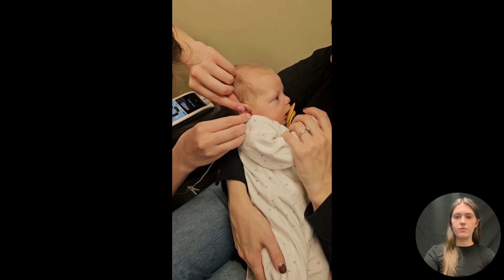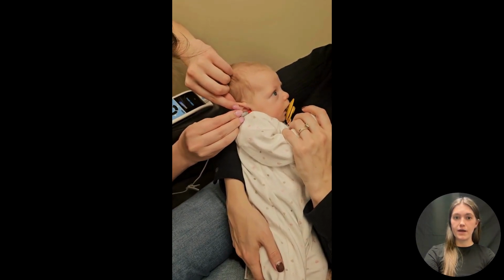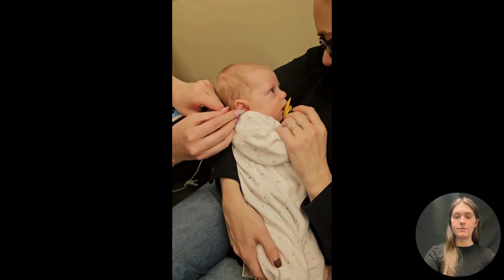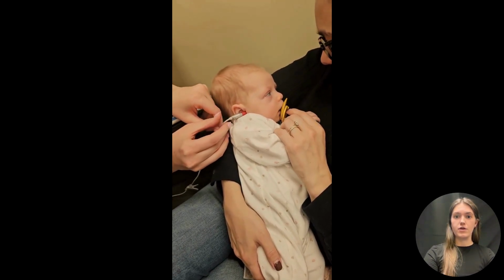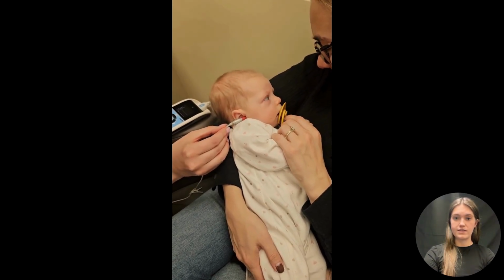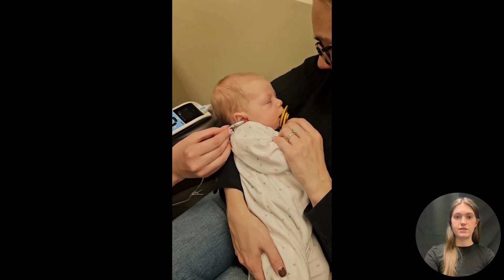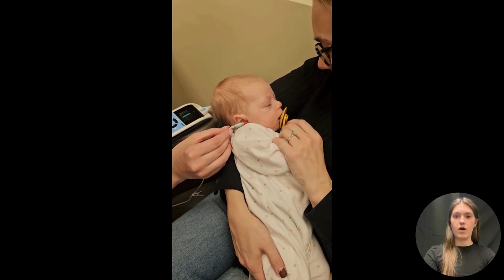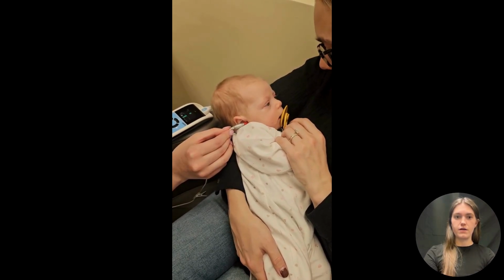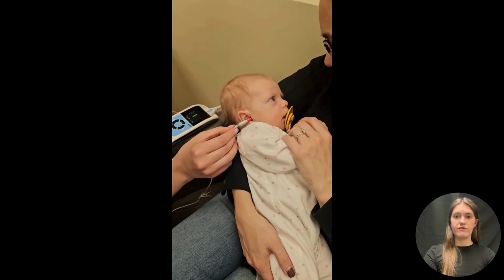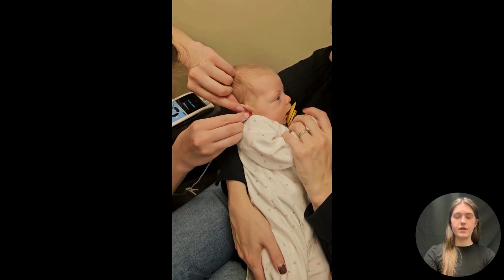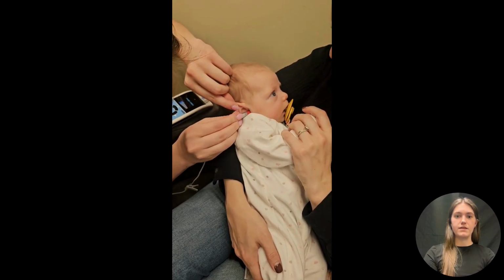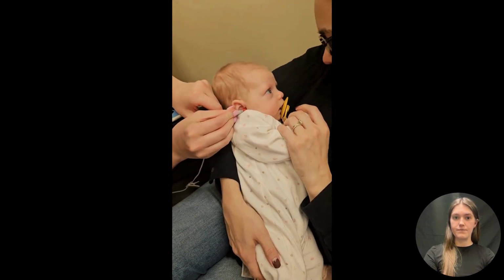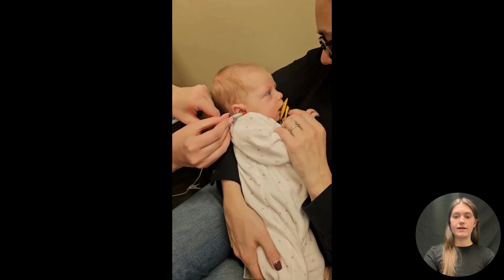To insert the probe, gently pull the ear up and back and push the probe tip into the ear canal. Do not hold the probe in the ear while testing. This can cause interference. Select the protocol on the OAE screen and start measuring. Look for a pass or a refer response on the screen. Do not measure multiple times in the same ear at the same time. This can result in incorrect measurements.